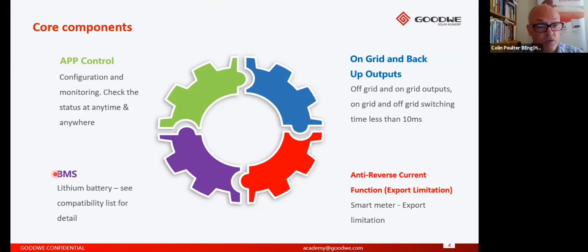All of our systems are lithium battery compatible, and the compatibility list is published on our website. All of our systems have an on-grid side and a backup side output, so in the event of a grid failure, within 10 milliseconds the backup port is available to supply essential circuits. Also common to all these devices is the ability to perform export limitation, also referred to in our documentation as anti-reverse current. This is achieved through our smart meter, which comes as part of the package when you buy it.